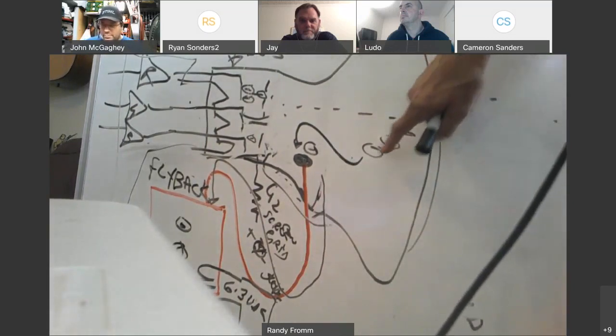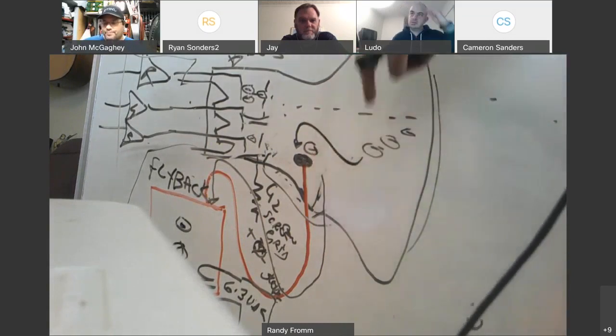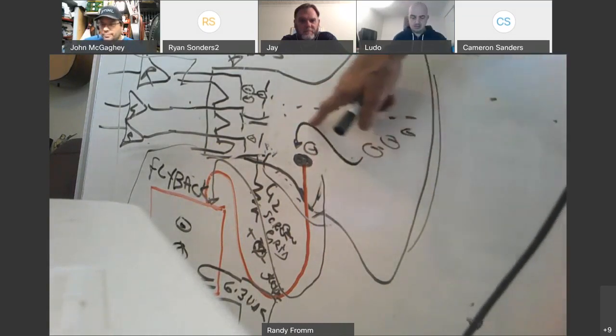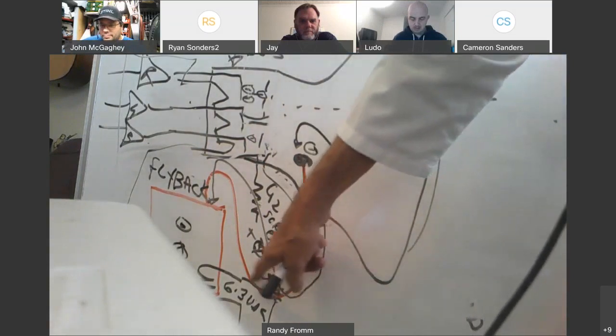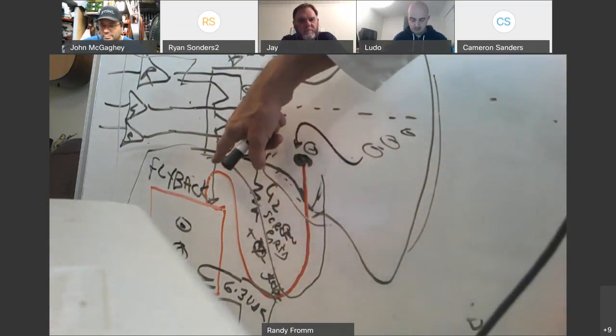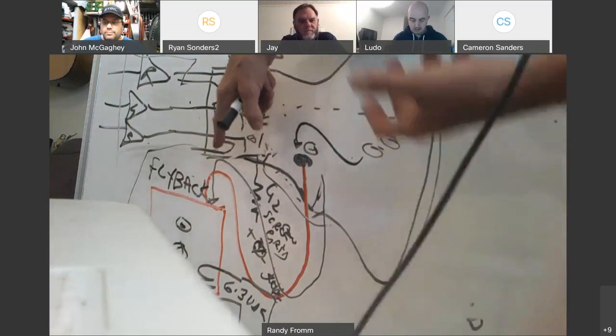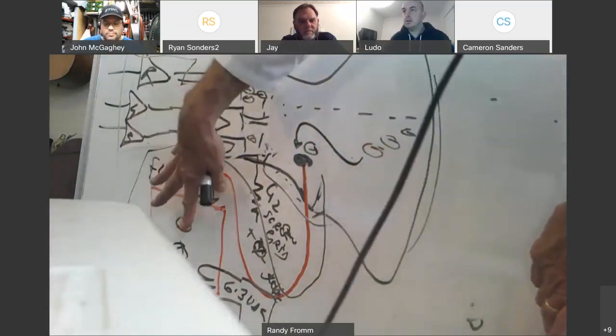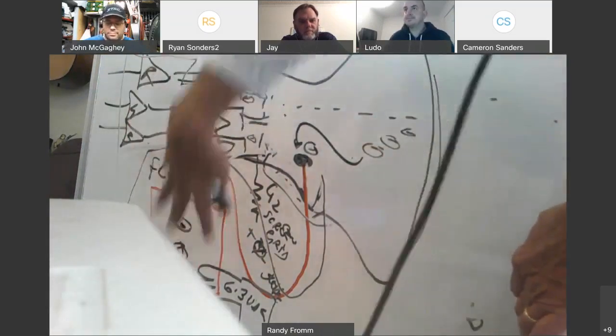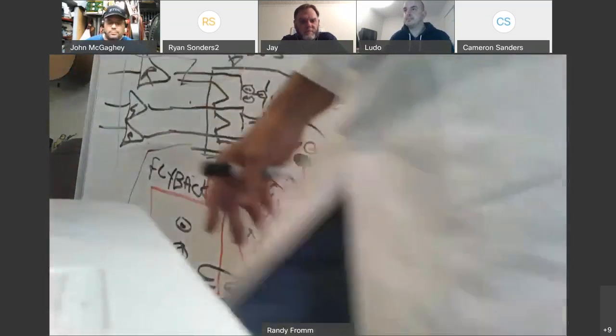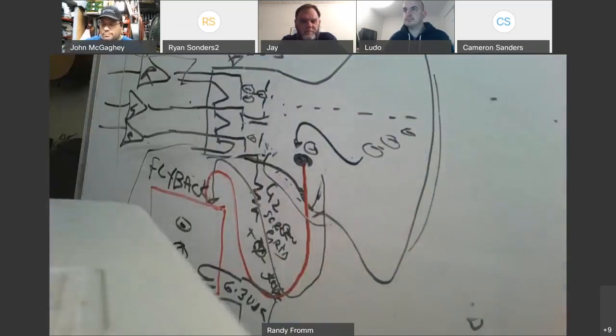So the electron is sucked out of the electron gun, out of the Aquadag, out of the second anode, along the heavily insulated red wire, which is really a thin wire, as you know, with a crap ton of insulation on it, into the high voltage unit, and eventually, if you look at the schematic, you'll see where it really connects to ground, and that's the purpose of that. Does that make sense so far? Everybody okay on that? Cool-o-matic? Yep. Okay, great.